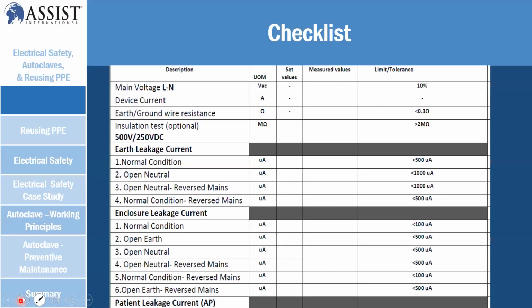So this is the checklist according to 60601 and 62353. You can use this for reporting purposes when you do electrical safety. So for device current, you have to measure device current, voltage, and earth ground wire resistance. Insulation test depends on the type of electrical safety analyzer that you use. Some are optional, some are built in together. And you have earth leakage current, enclosure leakage current, and patient leakage current.